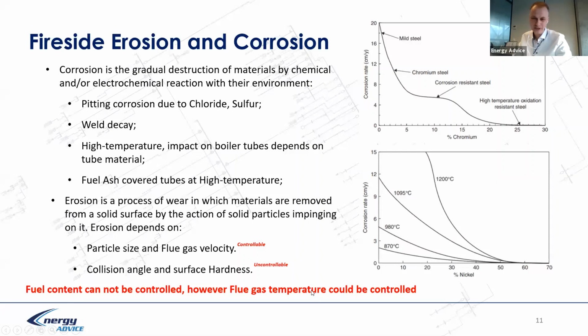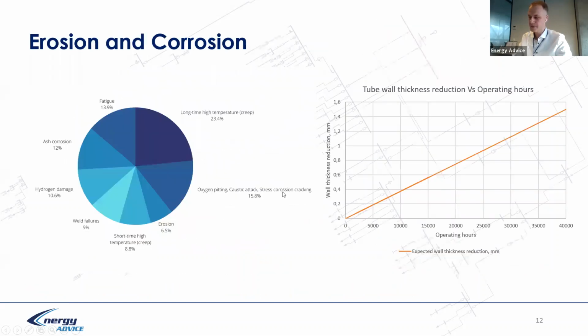However, flue gas temperature or the burning process can be controlled, and this makes an impact on the corrosion rate of your furnace. So with erosion and corrosion, we can understand the wall thickness reduction rate and operating hours. Probably we have a characteristic for each boiler. And if you look at the reasons for corrosion statistically, long-term high temperature and cracking, short-time temperature creeping, account for 30%, 40% of reasons. Ash corrosion would be related to the ash, and erosion could commonly be fatigue and hydrogen damage. So almost half of the reasons, or even a higher percentage, depend on the burning process.